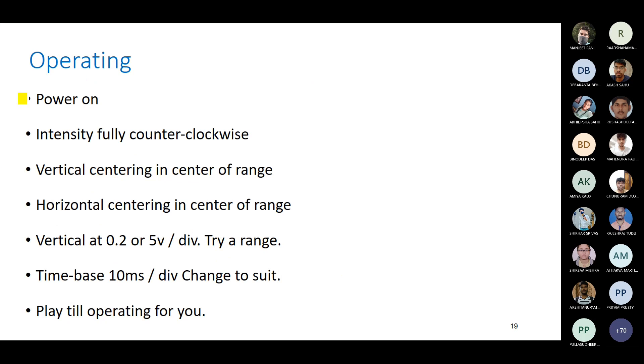For the operation procedure: first, turn on the power. Then set intensity fully counterclockwise — the intensity knob controls how many electrons are reflected to your screen. Increasing intensity means more electrons; decreasing means fewer. You need to balance both focusing and intensity — there is a trade-off between them. Centering and changing the range are also important steps.